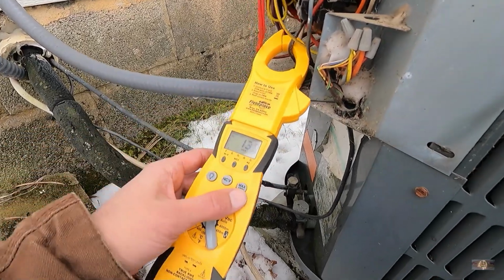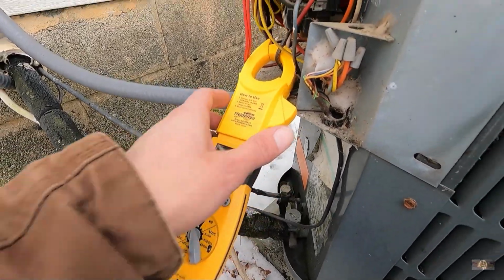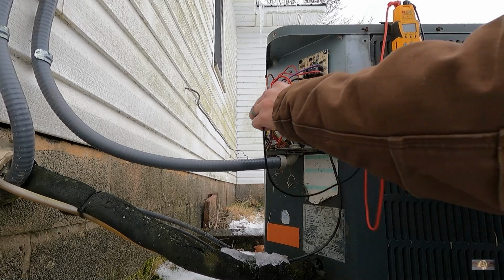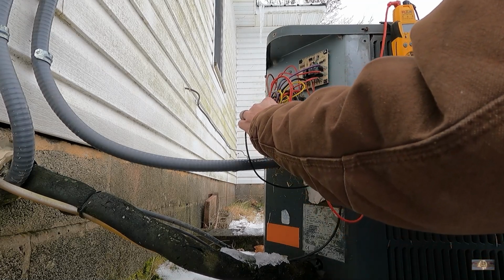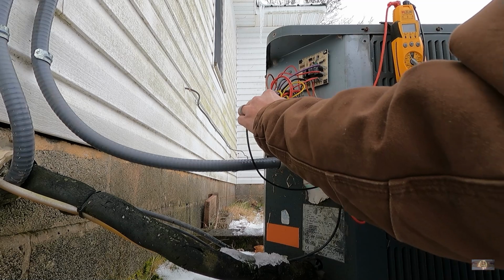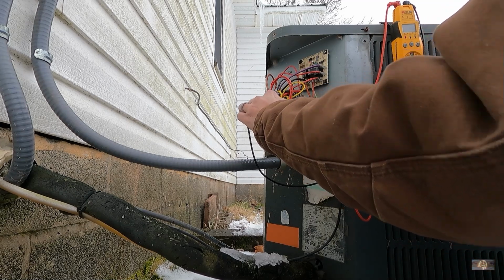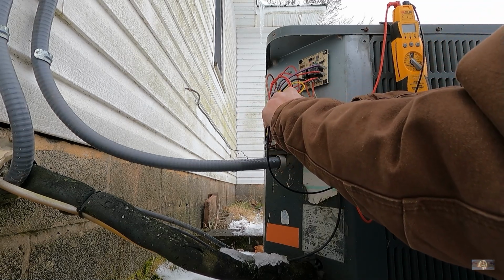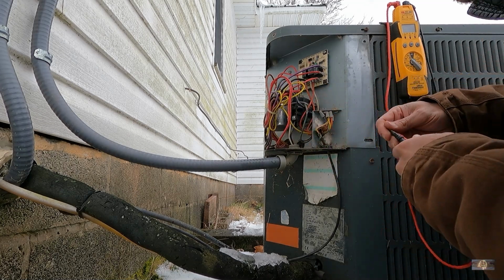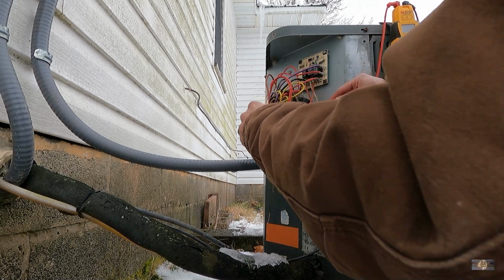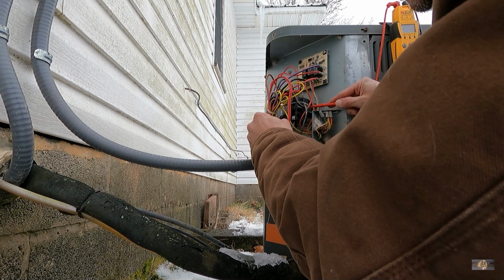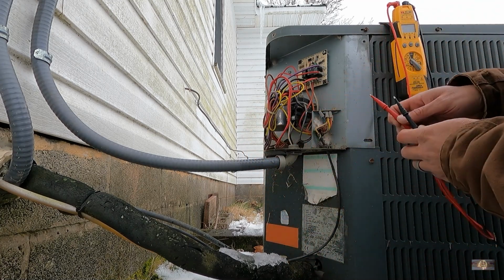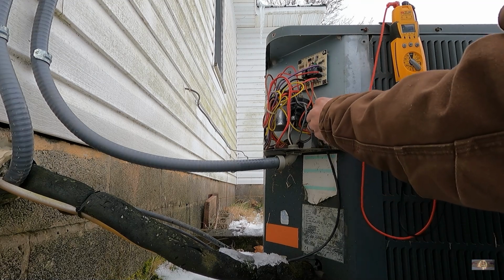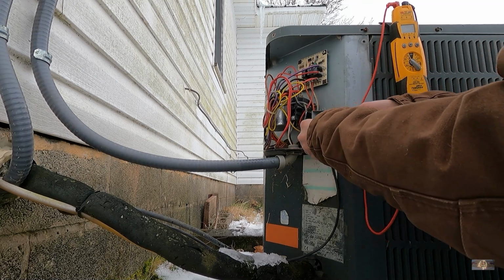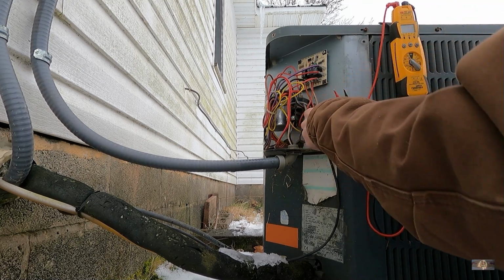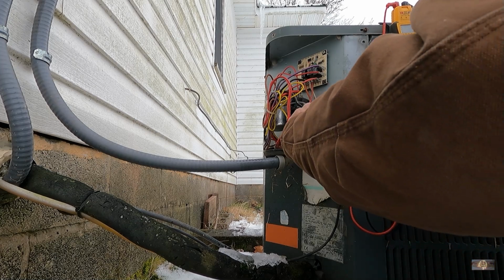Make sure we got some high voltage. Drew only 13 amps inrush. I'm not sure what's going on. Make sure we got high voltage here. 248, so we didn't trip a breaker or anything. Or a fuse. This is a fuse disconnect. Oh, my contactor is not pulled in. Shouldn't have 24 volts here then. And I don't. Let's see if we got 24 volts coming out here to the thermostat wires. I think she might have accidentally cycled the thing and we're in a time delay now.